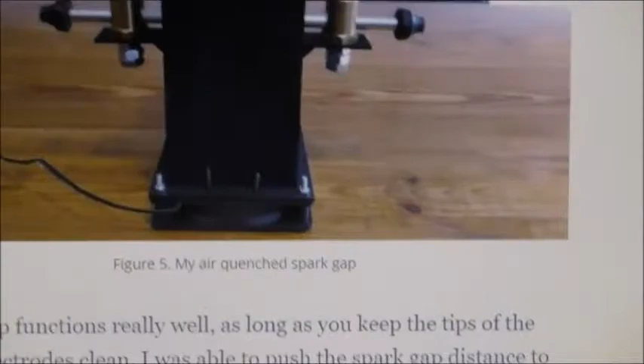It's talking about using thicker bars, because once you start talking about high frequency AC, radio frequency energy, you start getting something called the skin effect, where the high frequency current actually runs around the outside circumference of the bars. So the larger in diameter they are, the more efficiently they will conduct the high frequency AC energy. There's a bit there on standing waves. There's his improvement - so it doesn't quite look the same as it did before.